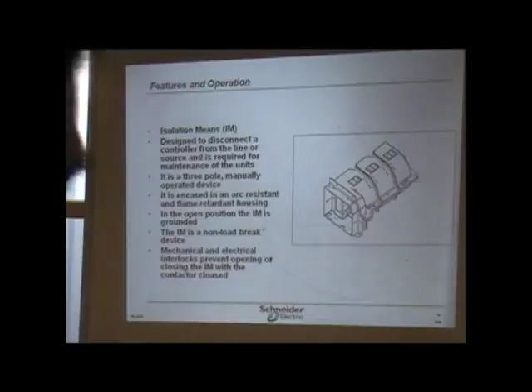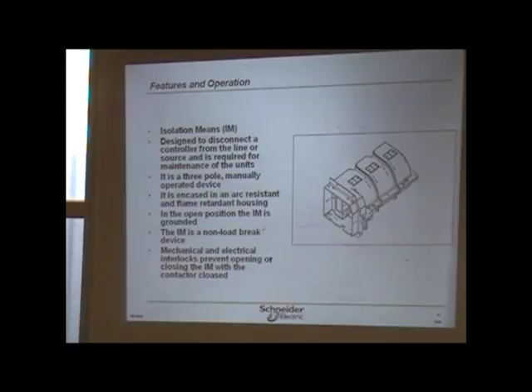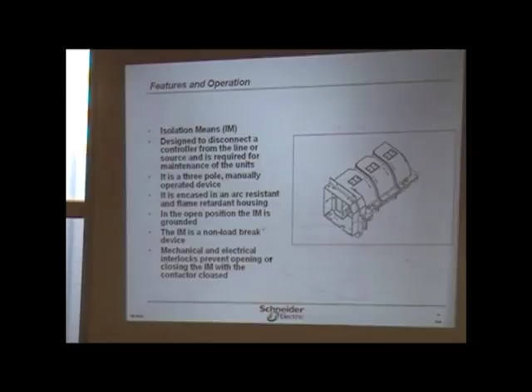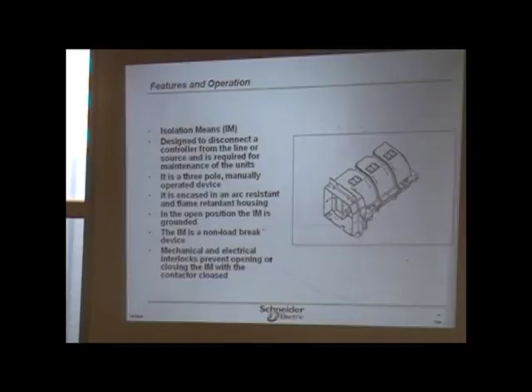You know, does it make sense? Yeah. Because it's a lot easier when you see it that way. You say, okay, it's just a one-line diagram. That isolating means is going to be like a switch, and then you have your contactor there as far as your contacts. So if the contactor is closed, you cannot open or close this right there. With the contactor being closed, there's no way. The contactor's got to be open or dropped, de-energized. So now you're able to open or close that isolating means. It's that simple. I know sometimes it can get confusing when you're looking at it and wondering, well, how can that be? More or less, your one-line will show that. Okay? And here it shows you that the blades of that isolating means are grounded.